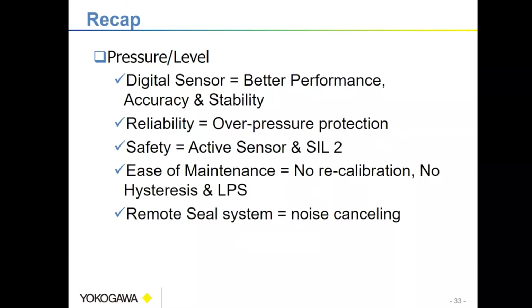And the fact that we're frequency based, we're more linear just in the nature. And we don't have to do all the characterization to our sensors like the other types of sensors require. So that allows us to do the larger turn downs and also avoid the calibration when you rearrange them. Because when you pick that new point for your span and zero, you have to adjust those to keep that fine accuracy. But with ours, you're able to cover the whole window of that capsule and meet the published specifications in the GS just by assigning a new zero and span setting.